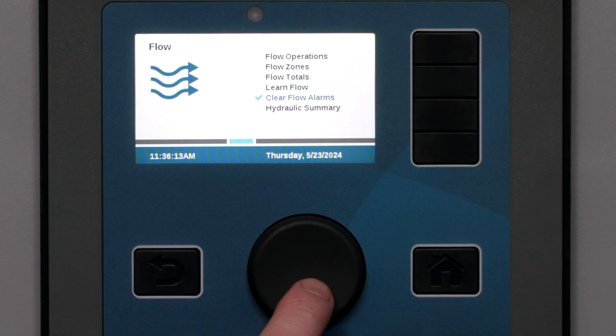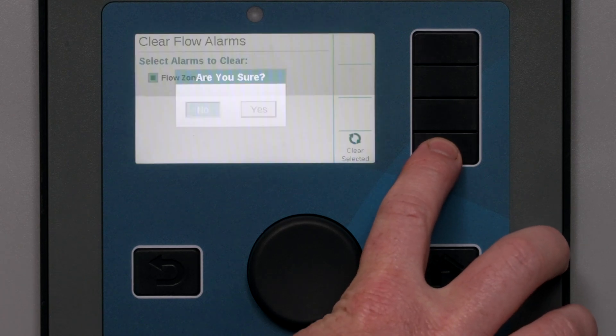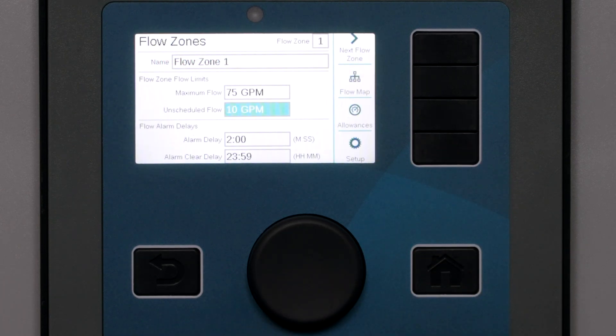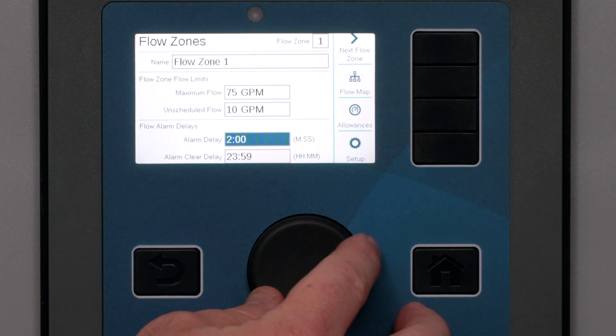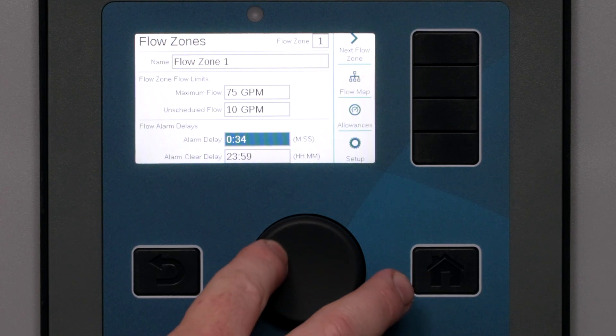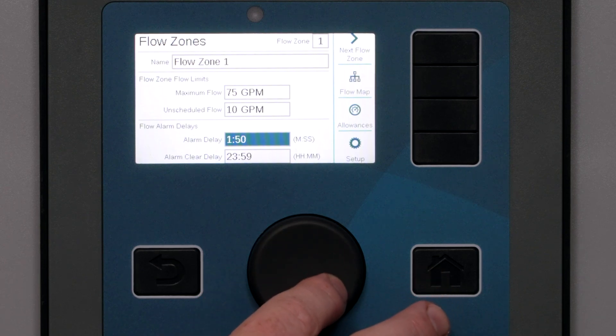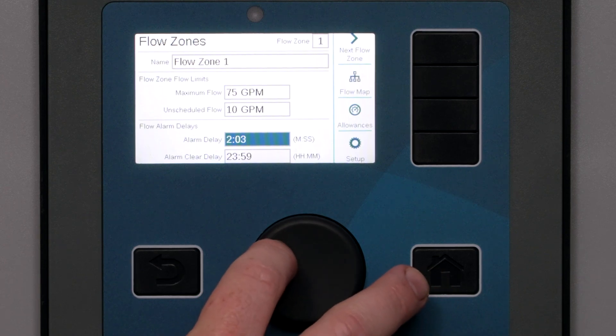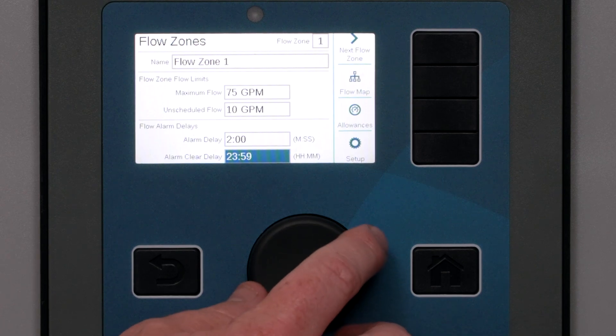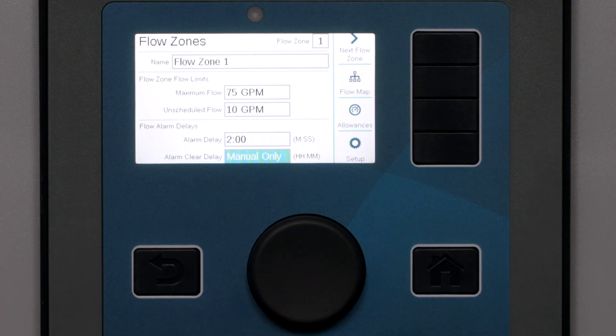The flow menu has a clear flow alarm selection for this purpose. If the system is prone to false alarms, you might want the flow zone to be able to run again after a 12-hour interval has elapsed. However, if the line is not fixed, it will alarm again. Manual only ensures that service personnel must physically visit and reset the controller, presumably after repairs are completed.